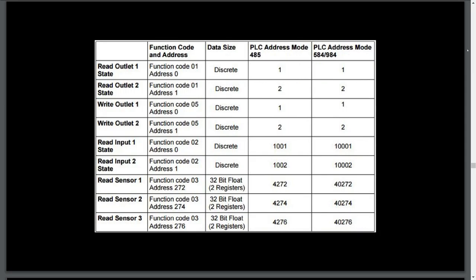If we want to see the state of the first outlet, we send a read coil or function code 1 address 0 request to the WebSwitch. For outlet 2, we simply change the address to 1. To change the state of an outlet, we issue a write single coil or function code 05.